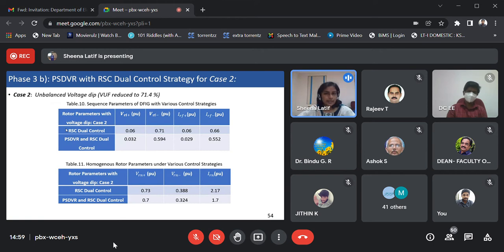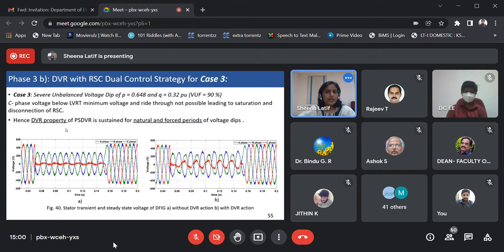With the combined method of PSDVR and RSC dual control strategy, the negative sequence rotor forced current is reduced to 0.55, and the natural component of the rotor current is reduced to 1.7 per unit. Considering the third case, which is VUF equal to 90%, as we have seen, one of the phases has already dropped to almost zero voltage, and here we cannot apply the PSDVR method of voltage decrement during the steady state condition.